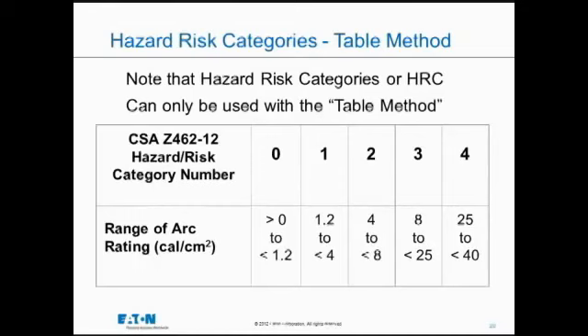They're only applicable if you use the table method, and that's the big key now in understanding the shift in thinking from reporting these values if you do energy analysis. So any of you that are doing energy analysis or getting arc flash analysis done should be aware that hazard risk categories cannot be used or should not be used when detailed analysis is done. It is still allowed if you're using the table method.